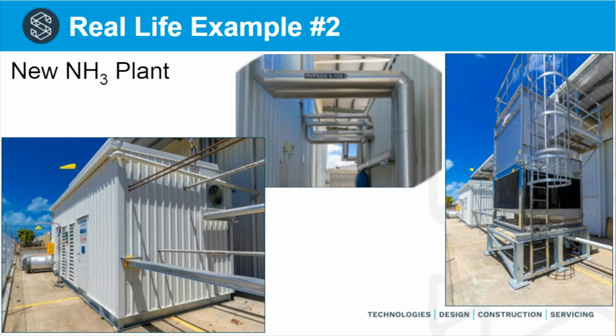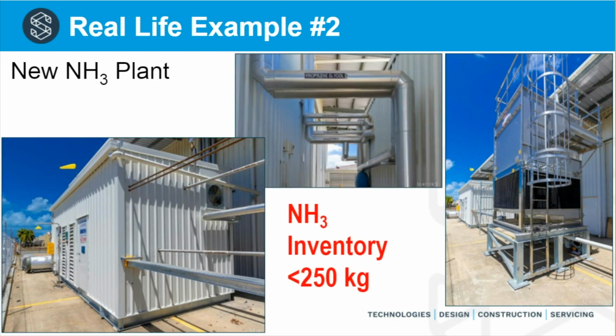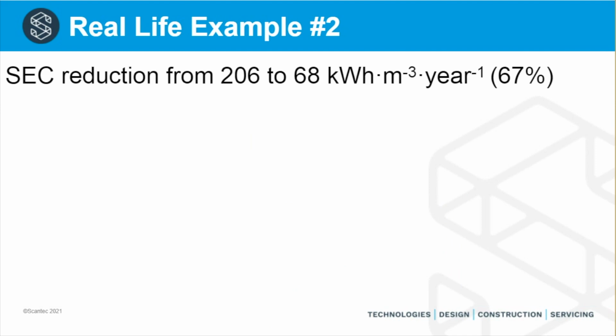You can see on the left-hand side there, you see the prefabricated plant room. The ammonia inventory is quite a bit less than 250 kilos. On the right-hand side, you see the evaporative condenser. And this reduced the SEC value from 206 to 68 kilowatt hours per cubic meters per year. Now, the 206 value is recorded, or was recorded, over 5 years prior to the Freon plant being shut down. So that value is quite real.